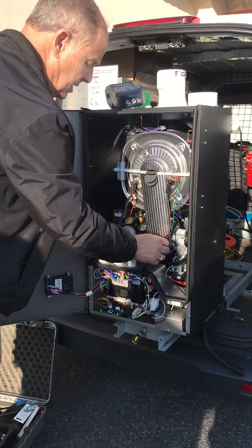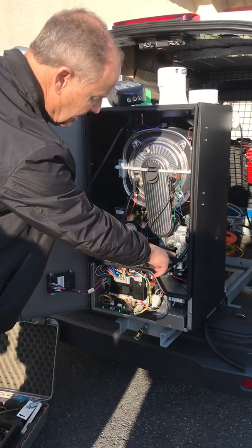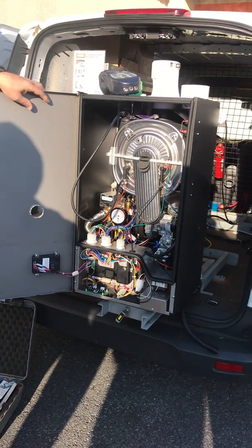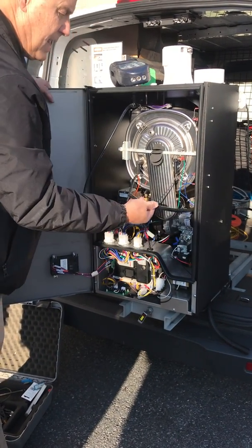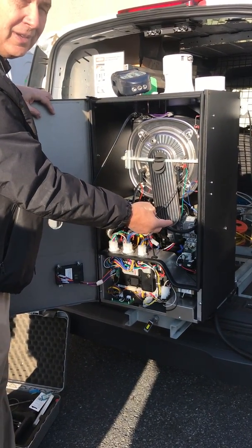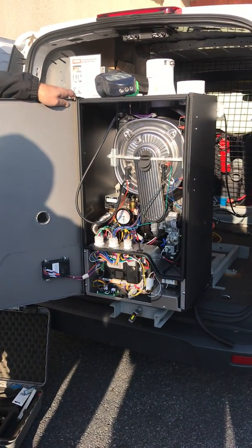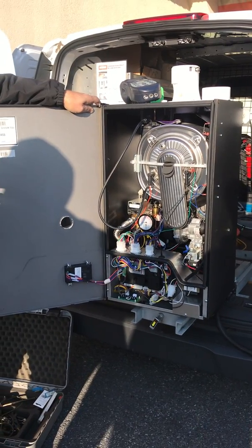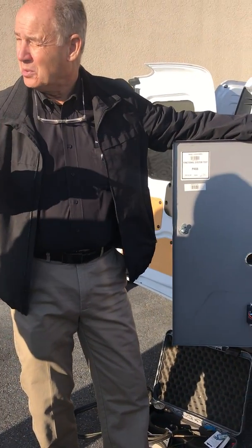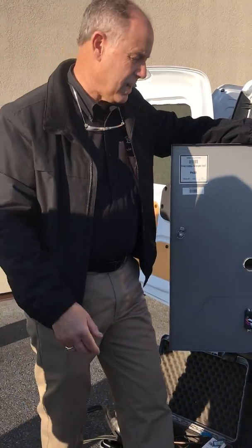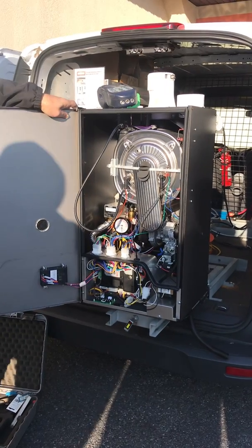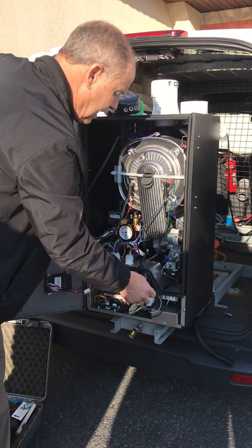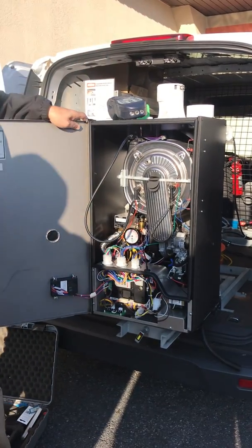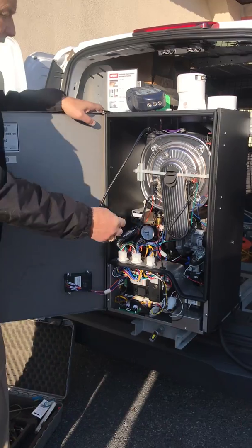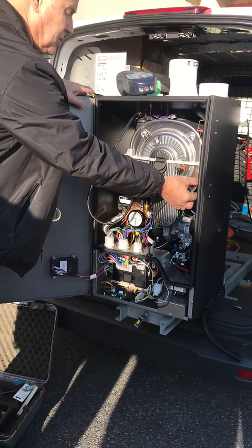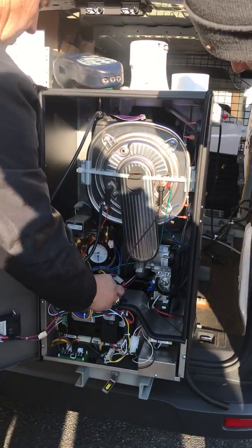What we do, however, this is my manifold tap. Right there, there's a pressure tap on the manifold. That pressure tap, when this starts up, this little pressure switch measures your manifold pressure, which is negative. What's manifold pressure on a standard gas boiler? Anybody? 3.5. Yeah. On these, negative 0.02. So I don't really ever check it. There's a little screw in there. If you don't get it to light, you want to check that screw and make sure it's backed out so that you actually get gas out of there when it goes to turn on. And this hose, if I'm not sure if my switch is bad, I can literally jump this out as soon as the blower starts. I can jump that switch.